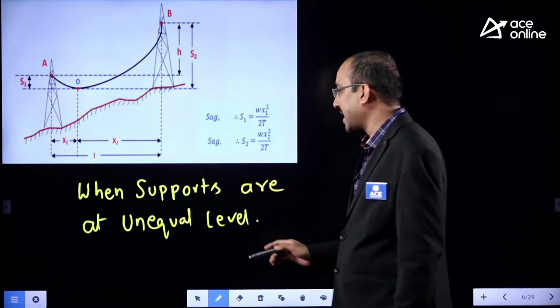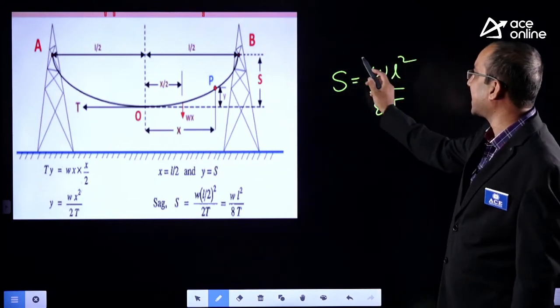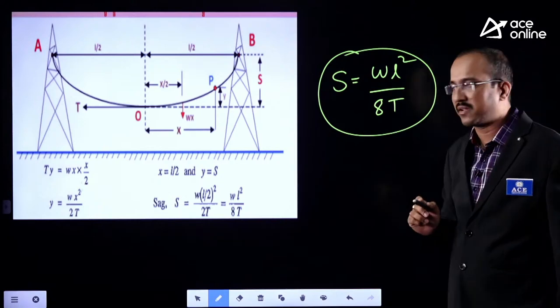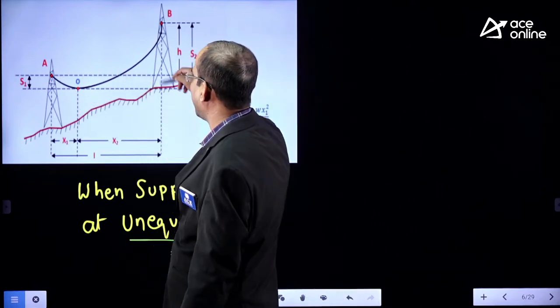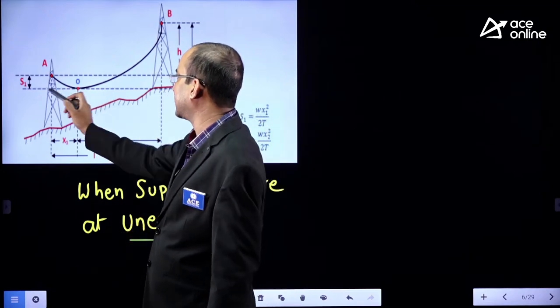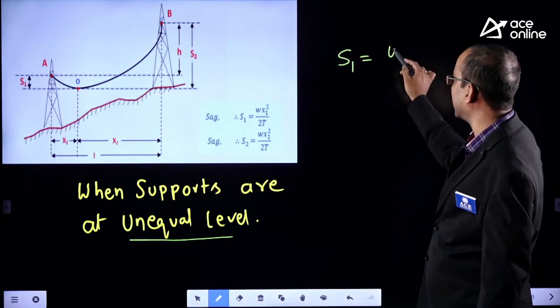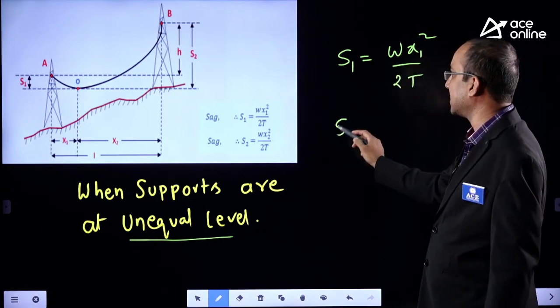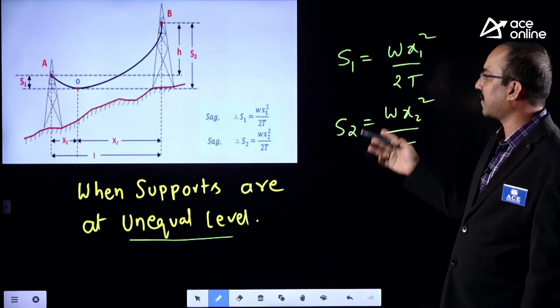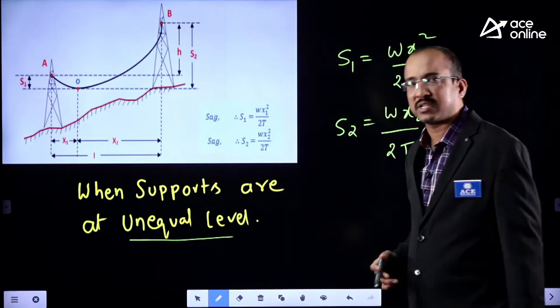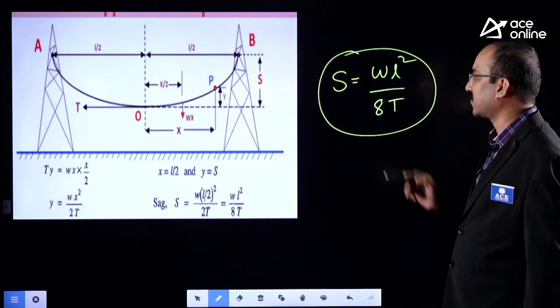When supports are at unequal level — for example, in a hill area — you will get two different SAGs. S1 is calculated as WX1² by 2T, and S2 is calculated as WX2² by 2T. When supports are at equal level, the SAG will be the same with respect to both towers, that is WL² by 8T.